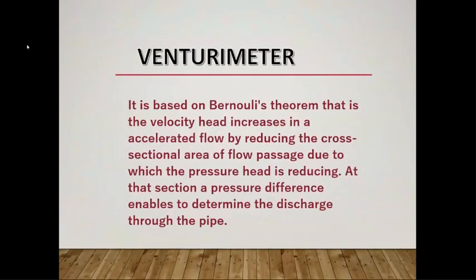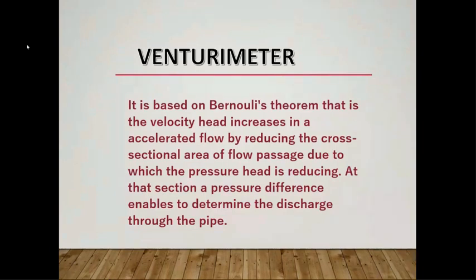The venturi meter is based on Bernoulli's theorem: the velocity head increases in an accelerated flow by reducing the cross-sectional area of the flow passage, due to which the pressure head reduces at that section. This pressure difference enables us to determine the discharge through the pipe.